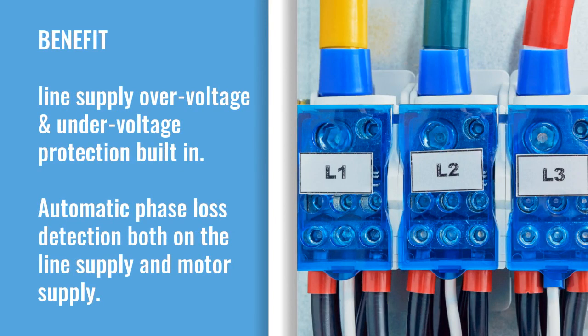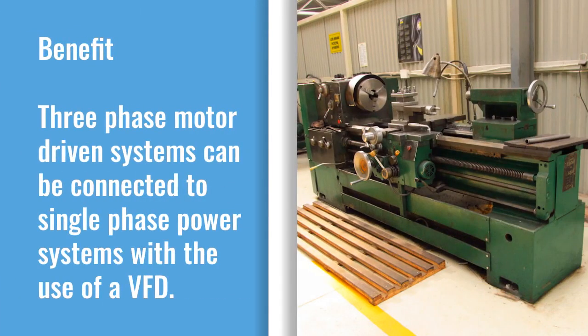Line supply over-voltage and under-voltage protection is built-in. Also, automatic phase loss detection is provided both on the line supply and motor supply. Additionally, three-phase motor-driven systems can be connected to single-phase power systems with the use of a VFD.